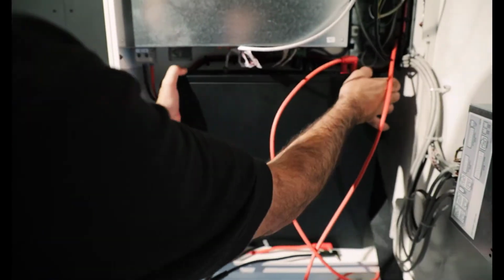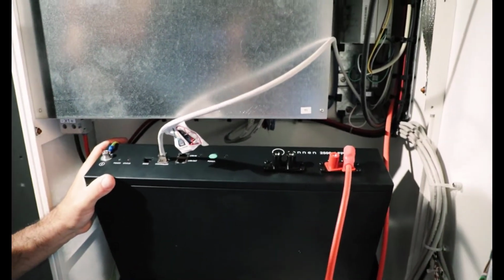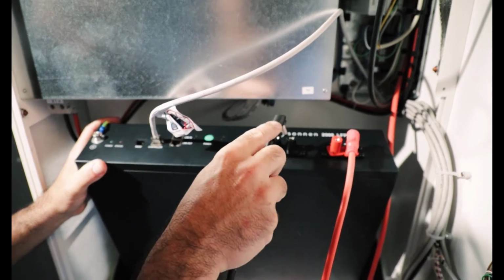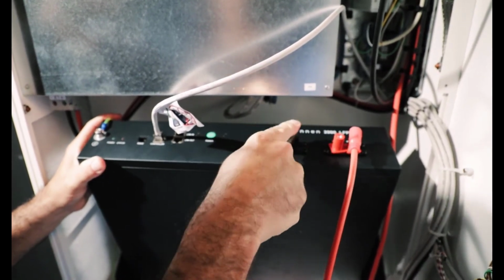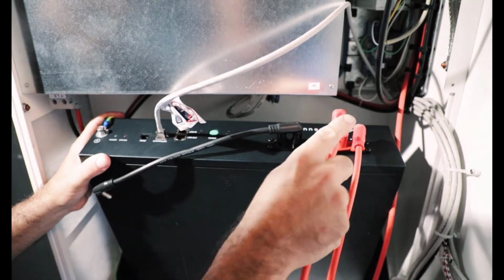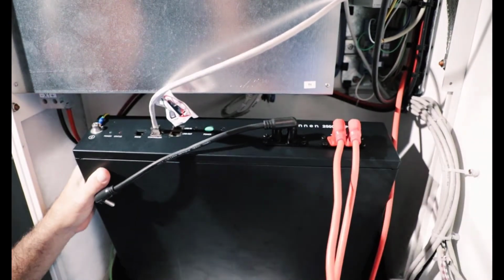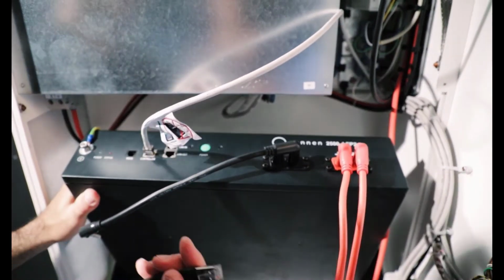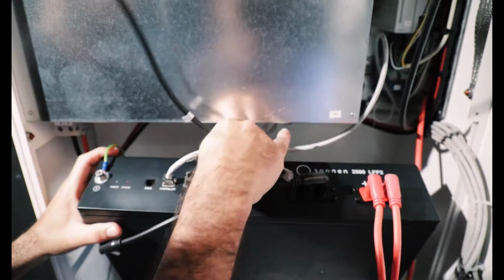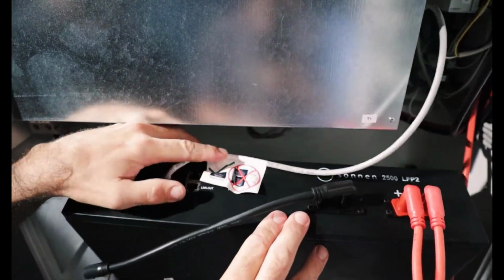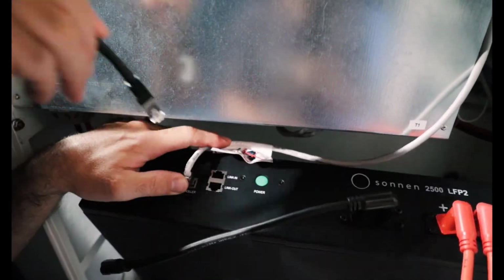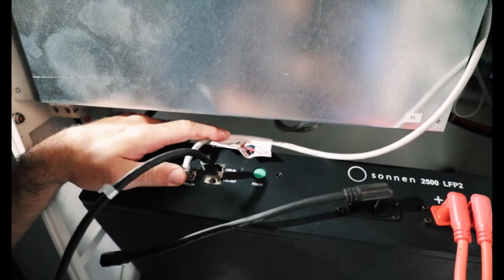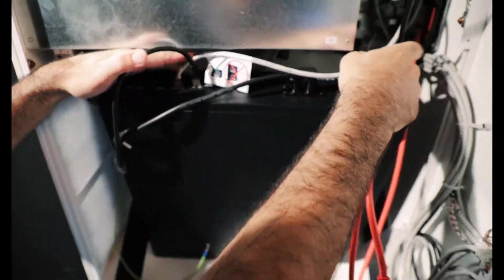Now these batteries come and although they have about 85% state of charge, they are turned off and they only actually turn themselves on once the sonnen system tells it to. So although, as you can see here, we've just plugged in the positive and negative and they have exposed terminals, the battery is for all intents and purposes off, so there's no danger of any exposed live parts. We also then plug in the C-bus cable.